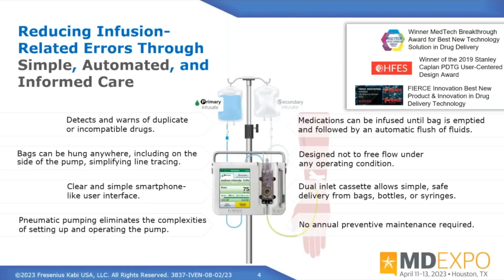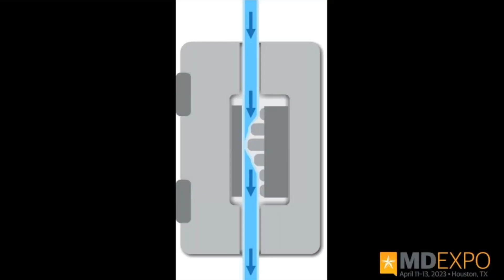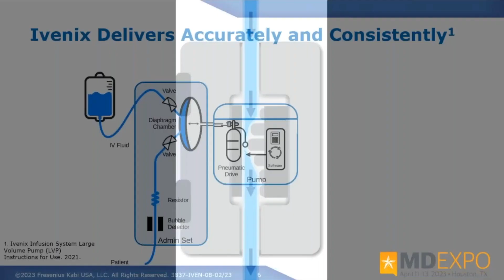So I talked about peristaltic technology. I always liken it to the idea of a child stepping on a garden hose and you get the squirt of fluid out. So peristaltic technology for infusion pumps works in a very similar manner, like squeezing toothpaste through a tube, applying pressure to get fluid to move through a system. We took a completely different approach. So that diaphragm-shaped chamber you see there, the IV fluid comes in. There are valves controlling the flow of that fluid on the other side of that diaphragm. And then that pneumatic drive is driven by software that accurately controls and is calibrated throughout that chamber push to push the fluid into the patient.